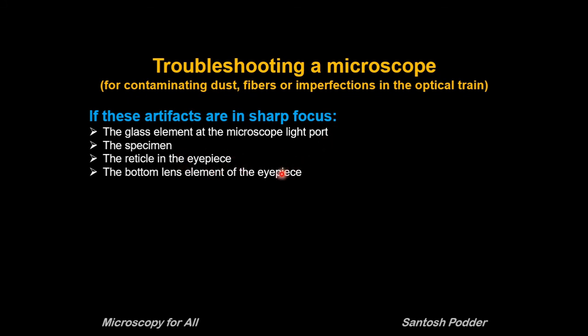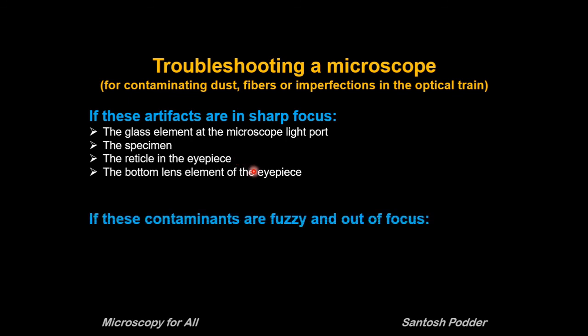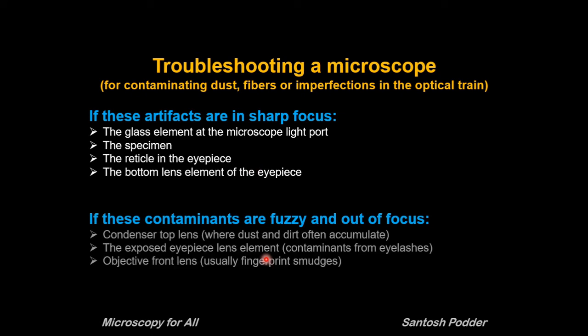You can also check the specimen or the reticule in the eyepiece — the reticule in the eyepiece always remains in the intermediate image plane, so you can easily identify it — and then the bottom lens element of the eyepiece. If the contaminants are fuzzy and out of focus, look near the surfaces that are part of the illumination planes, such as the condenser top lens where dust and dirt often accumulate, the exposed eyepiece lens element which often gets contaminated from eyelashes, and the objective front lens where fingerprint smudges are common.